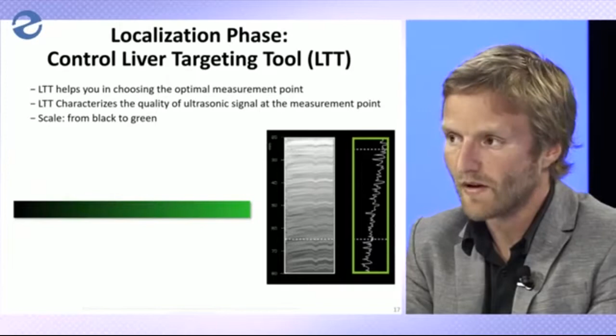And you have this indicator that we call the LTT, liver targeting tool, that will give you an indication of how good your ultrasound signal is at the current measurement point. So it's really important that this bar or frame, depending on your software version, is intense green. Intense green means that your positioning is good, and if you have the layers plus this green bar, you will ensure a good position. It will save you time for the examination.